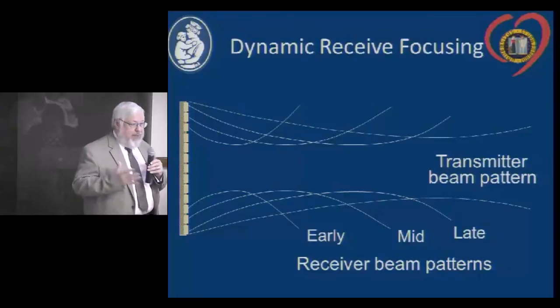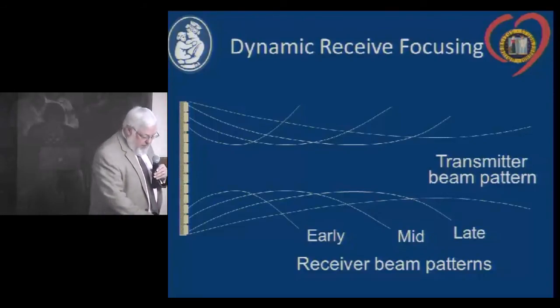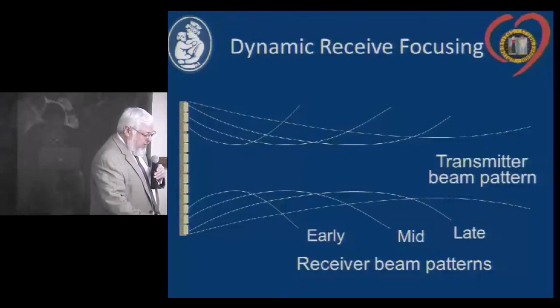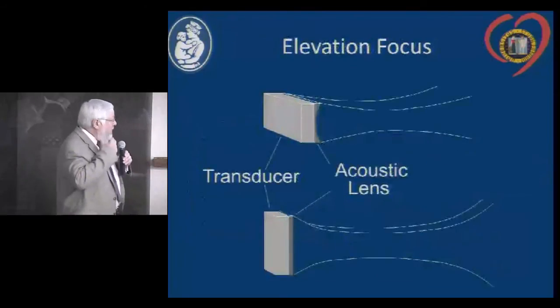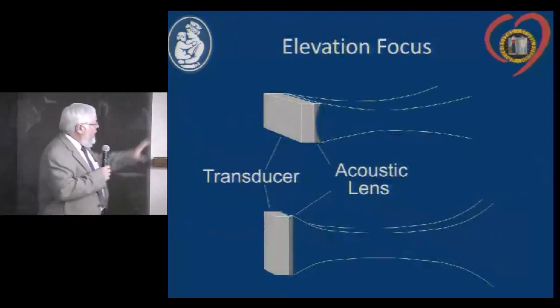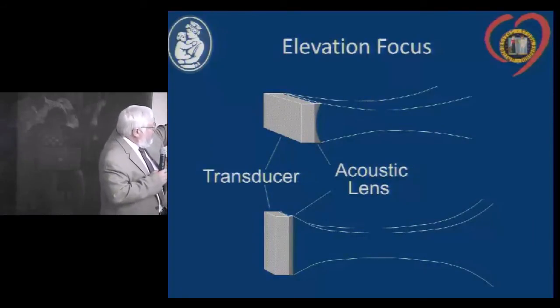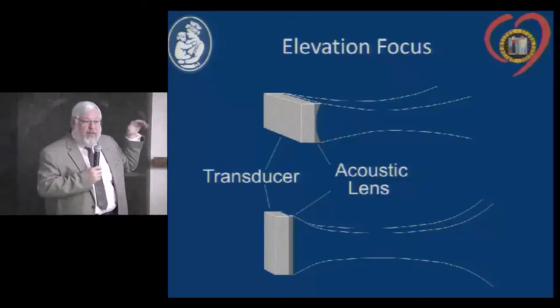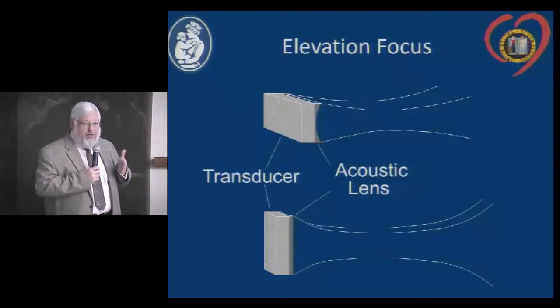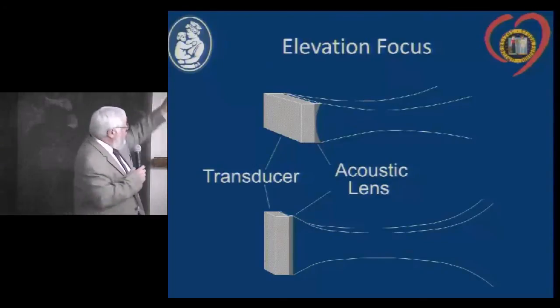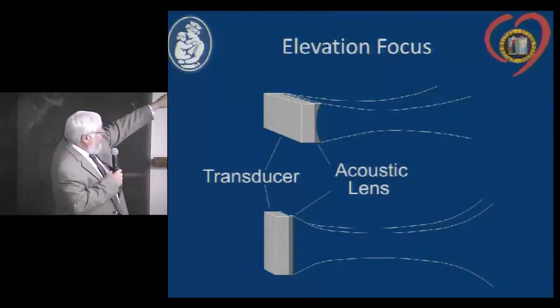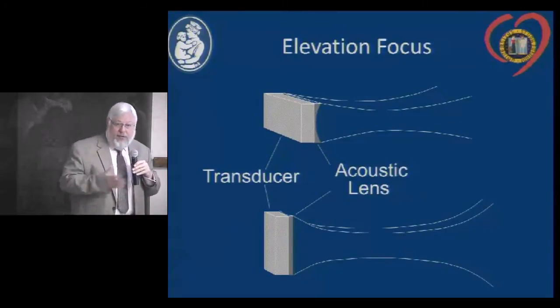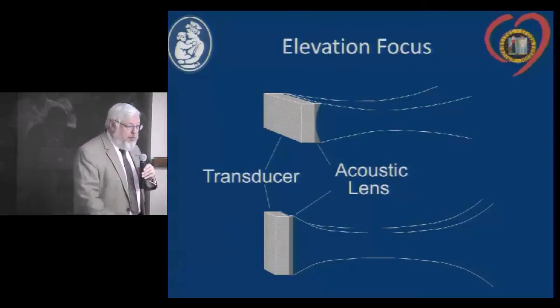Dynamic receive focusing was developed years ago and modifications are still used today for improving ultrasound image quality. This type of focusing occurs within the long axis of the transducer. To focus in the perpendicular dimension — perpendicular to the plane of the image — one must still use an acoustic lens placed on the front of the transducer.